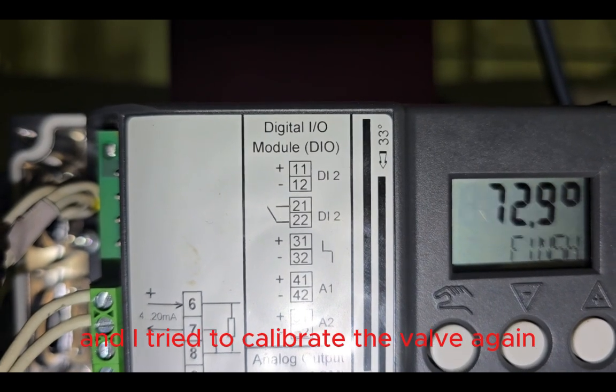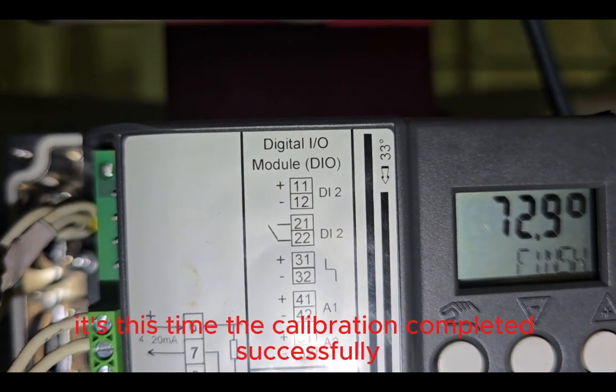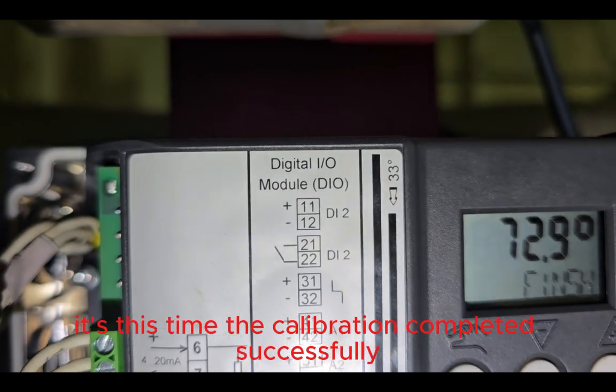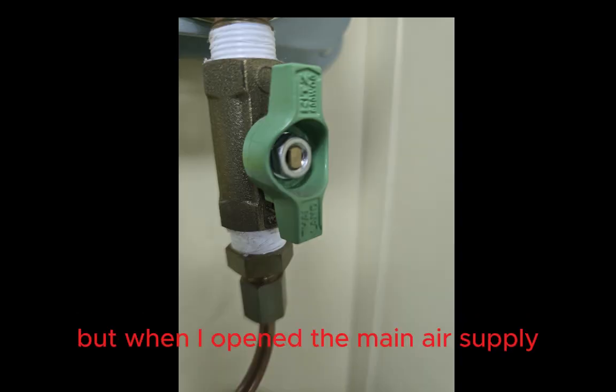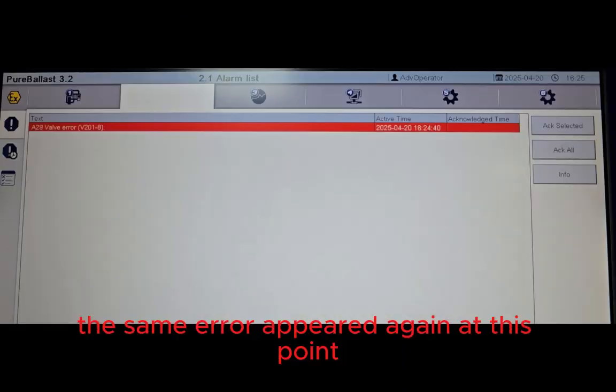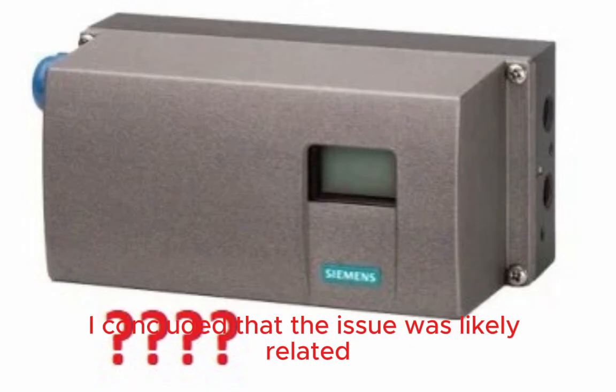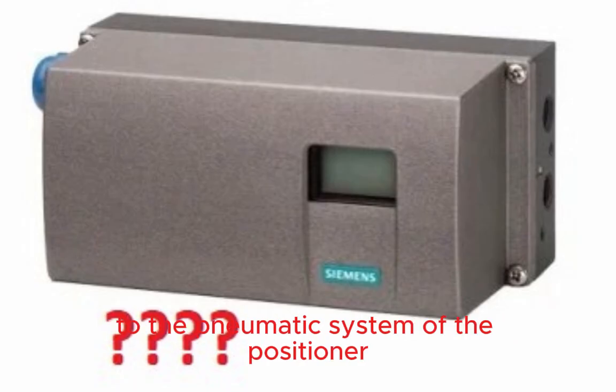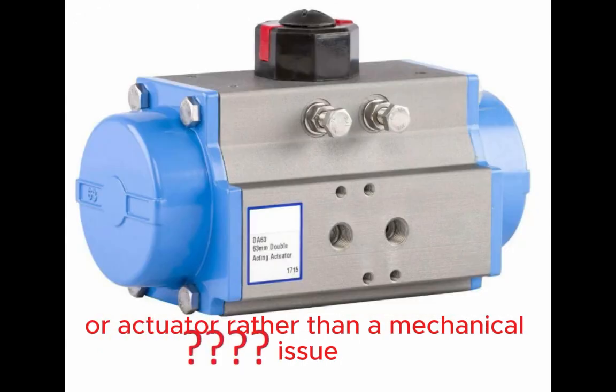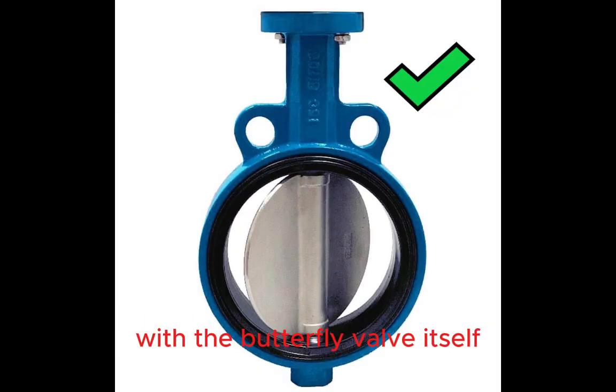Then I tried to calibrate the valve again. This time, the calibration completed successfully. But when I opened the main air supply, the same error appeared again. At this point, I concluded that the issue was likely related to the pneumatic system of the positioner or actuator, rather than a mechanical issue with the butterfly valve itself.